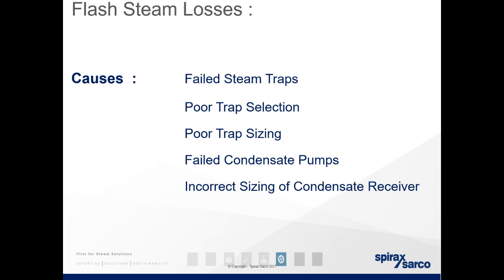So causes. Failed steam traps is another example of where you can start to see flash steam loss. On average, I only have the figures in dollars, but a leaking failed open float trap, for instance, will lose around 12 kilograms an hour. That translates to roughly about $52,000 a year in lost revenue. That's based on more of a European market, European costs, but we can also calculate these losses for you. If you get in touch with us and we come see your system, we inspect your traps, we can tell you how much money you're losing just from your failed traps.